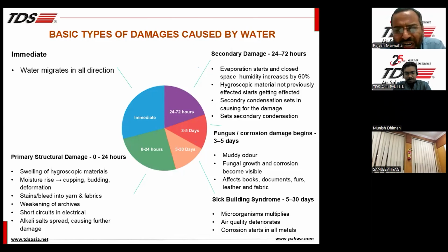The fungal corrosion damage begins later. We sometimes receive claims after 7, 10, or even more than 15 days, where we tell the surveyor, insurance company, or customer that we need to see the equipment before giving any quote or final decision. By then corrosion damage has already occurred inside the equipment — panels damaged, wiring damaged, fungal growth and corrosion inside. There's also sick building syndrome, where air quality deteriorates and most corrosion takes place inside the metal equipment. This is the last stage, where functional damage of the equipment occurs.